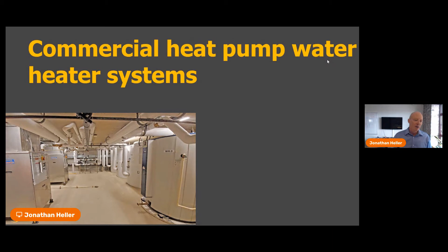The compressor you can see there on the left-hand side of this large commercial heat pump water heater. We've got a controls package, we've got storage shown there in multiple tanks, and finally we've got the backup electric emergency temperature maintenance heating system, shown here in this larger built-up system as a temperature maintenance loop tank with electric resistance backup.